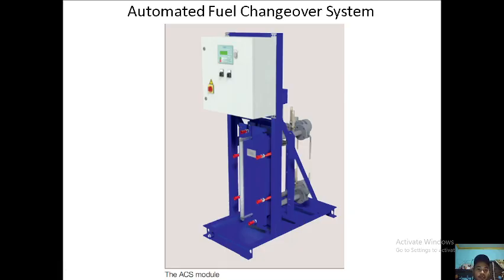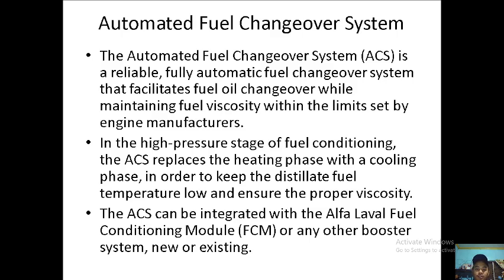So we have the automated fuel changeover system. The automated fuel changeover system is a reliable, fully automatic system that facilitates fuel oil changeover while maintaining fuel viscosity within the limits set by the engine manufacturers. In the high pressure stage of fuel conditioning, the ACS replaces the heating phase with a cooling phase in order to keep the distillate fuel temperature low and ensure the proper viscosity. The ACS can be integrated with the Alfa Laval fuel conditioning module or any other booster system, new or existing.